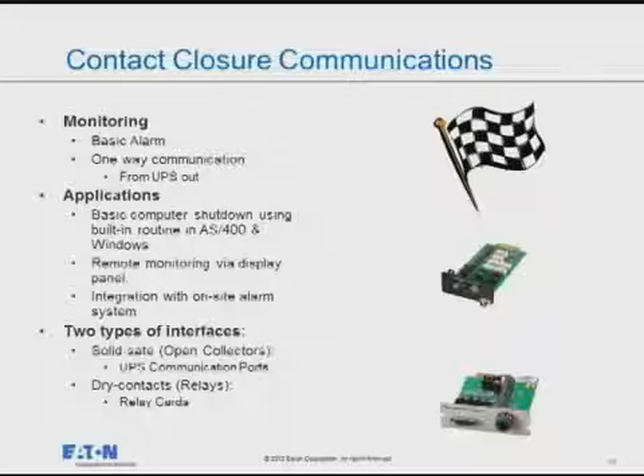When we talk about contact closures, I'm really talking about a flag symbol. From a UPS perspective there are really four alarms: UPS available, UPS on bypass, UPS on battery, and UPS on low battery—meaning you're about to shut down permanently. Those are the typical four relays, just yes/no signals, giving you eight pieces of discrete information. It's of value, but limited value at best.